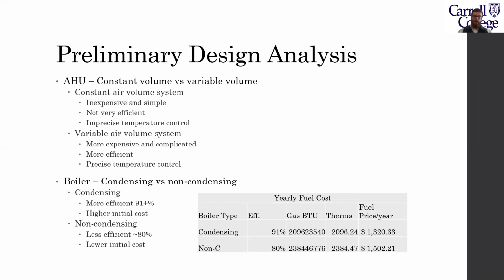into a zone. A variable air volume system is more expensive and complicated, but it's more efficient and provides more precise temperature control. This is because, in addition to changing the temperature of the air going into a zone, you can also change the amount of air going into the zone. And because the fans don't have to operate at maximum speed the whole time, it is more efficient.